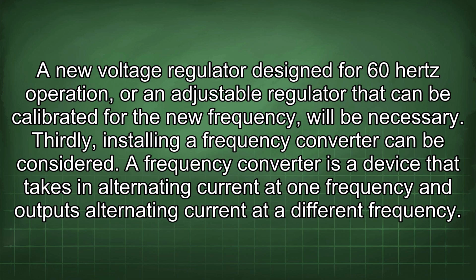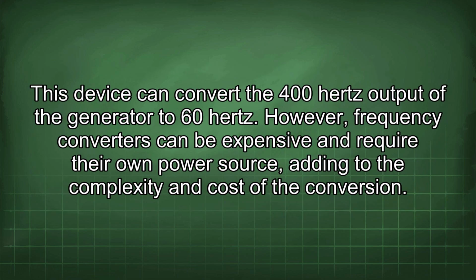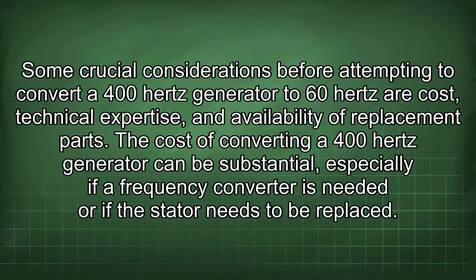A frequency converter is a device that takes in alternating current at one frequency and outputs alternating current at a different frequency. This device can convert the 400 Hz output of the generator to 60 Hz. However, frequency converters can be expensive and require their own power source, adding to the complexity and cost of the conversion. Some crucial considerations before attempting to convert a 400 Hz generator to 60 Hz are cost, technical expertise, and availability of replacement parts.